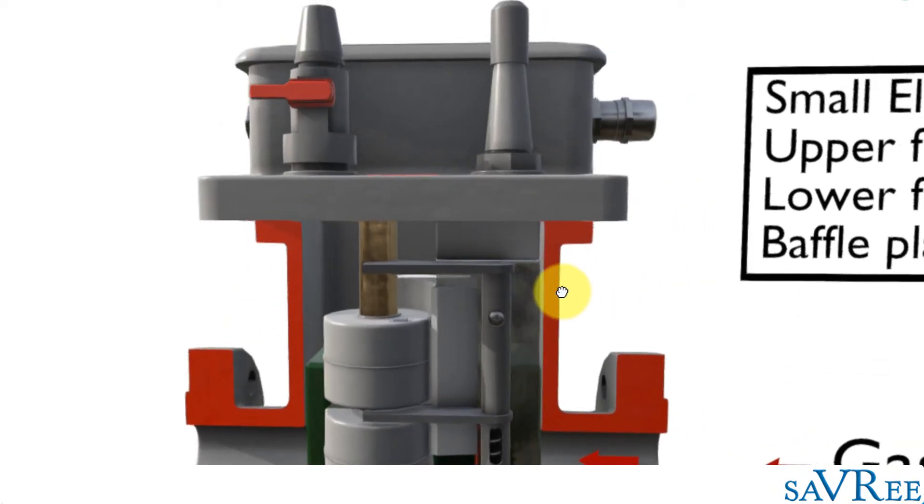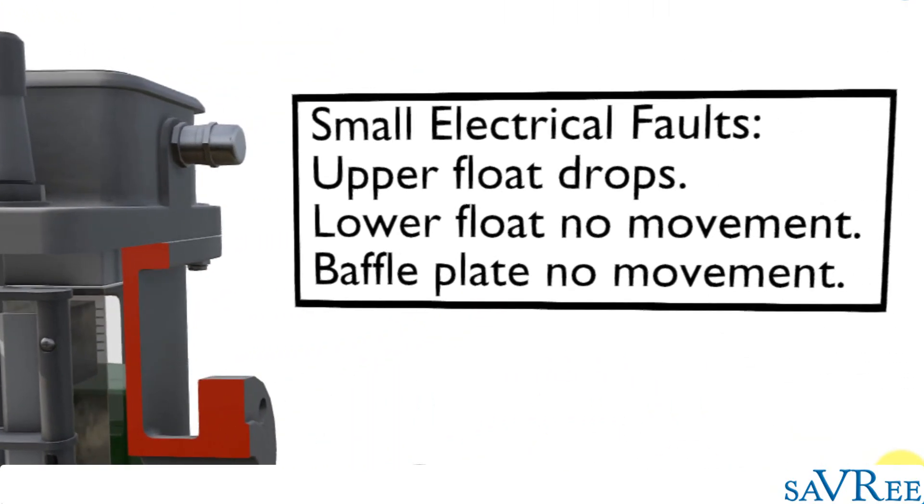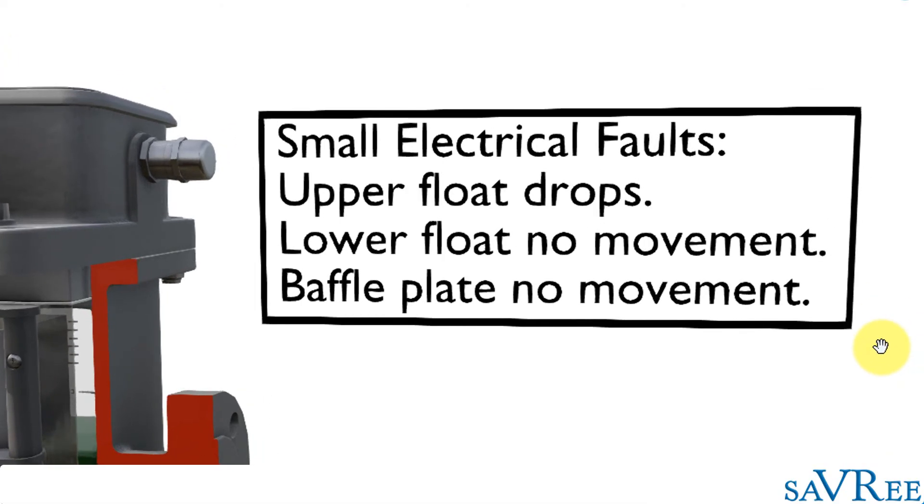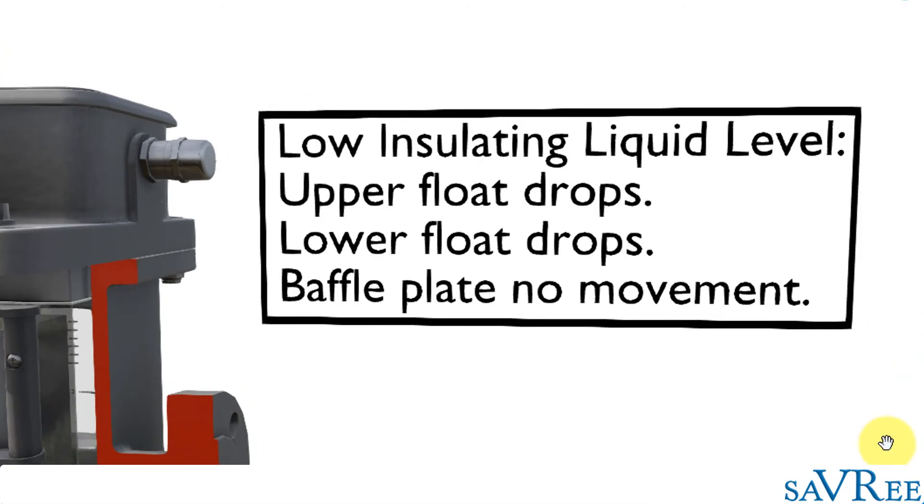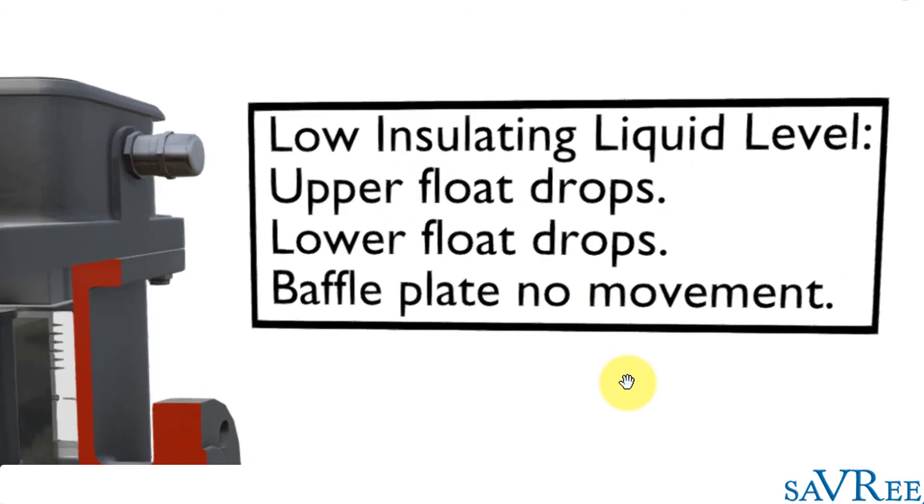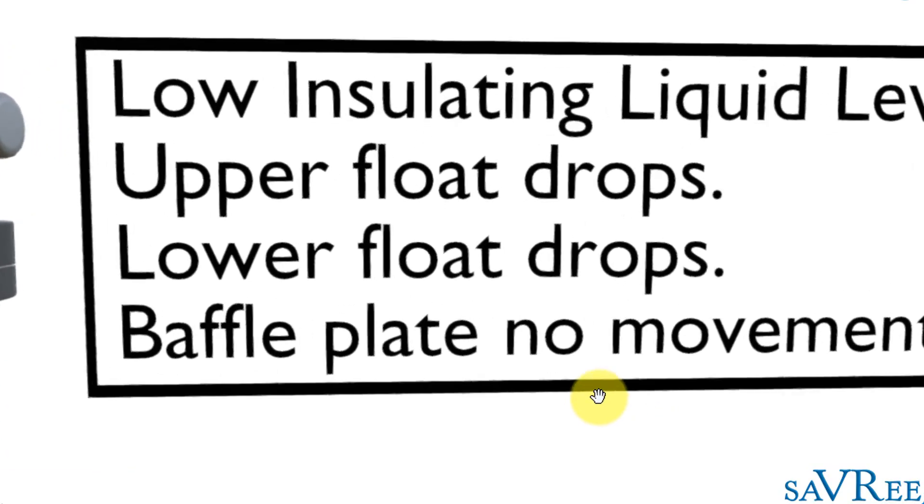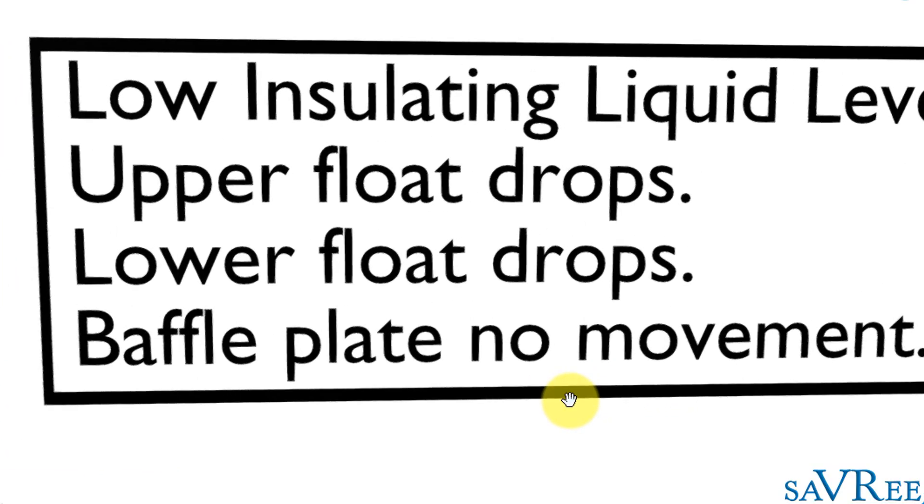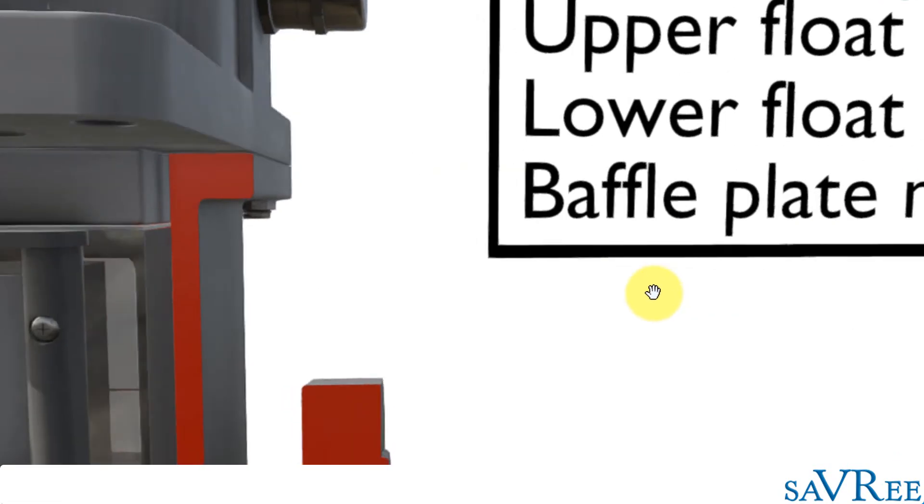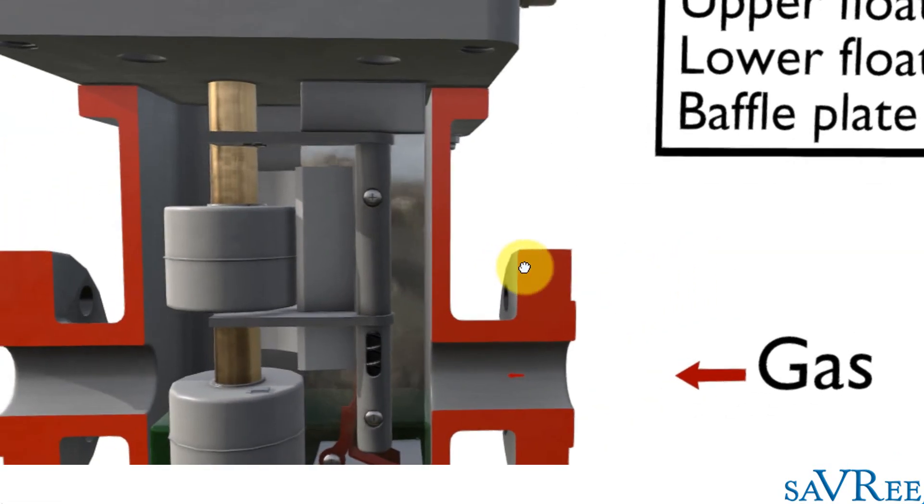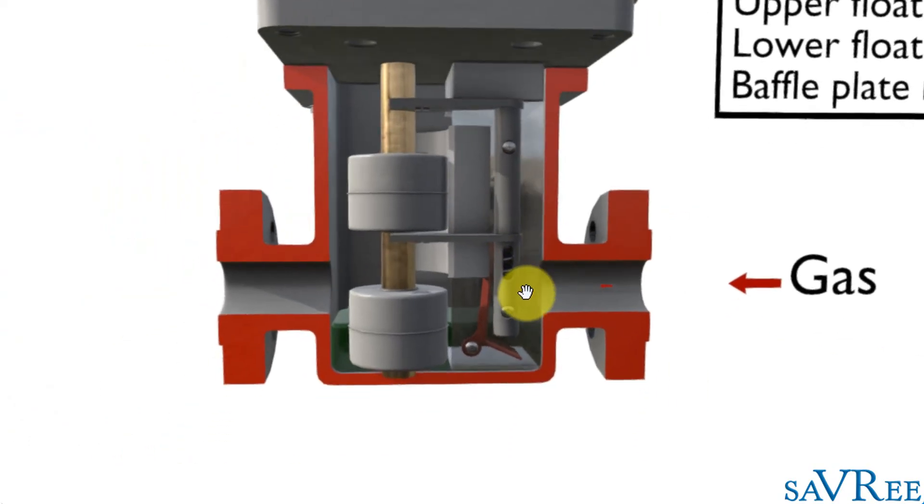If we go back out, we've got one more type of fault. Low insulating liquid level, upper float drops, lower float drops, and baffle plate, no movement. So different combination here, but a different kind of fault. The baffle plate we can ignore because it's only used for one type of fault.